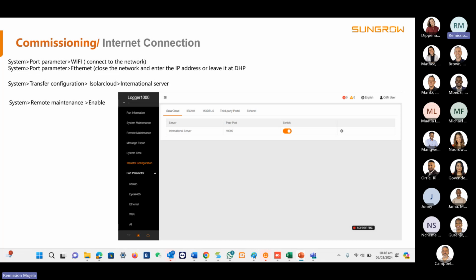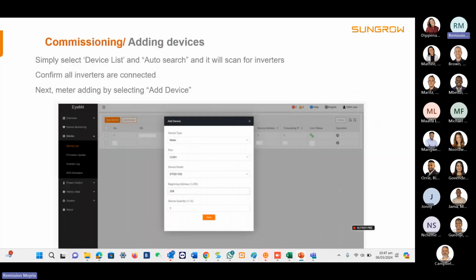Same thing with other devices basically, but one important thing is that the system must be under the international server, and to be able to change settings remotely, you need to enable the remote maintenance, which is something that we can do remotely as well, but it's easier that you just do it when you're commissioning so that you can change settings remotely immediately.